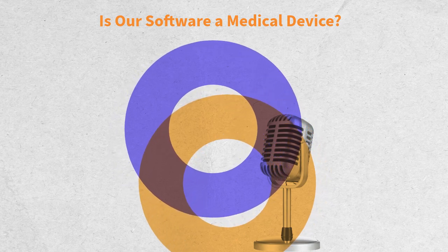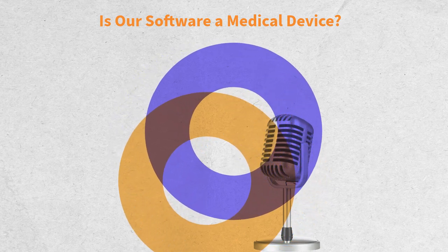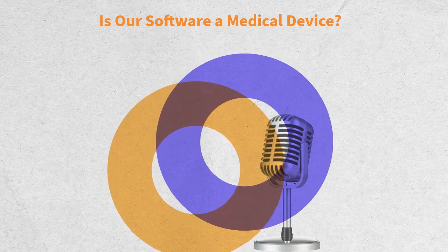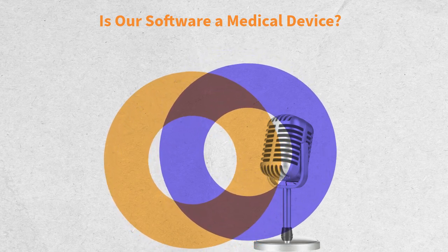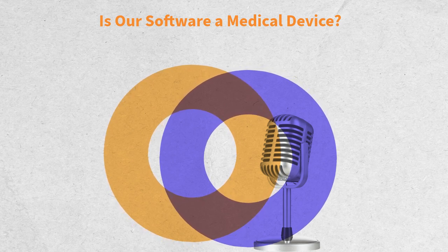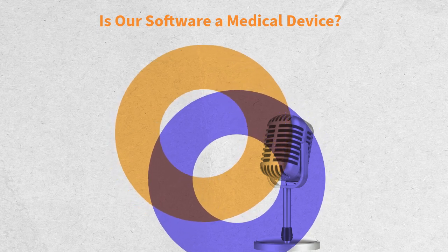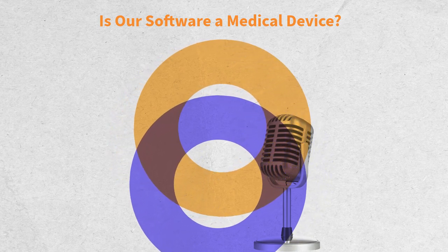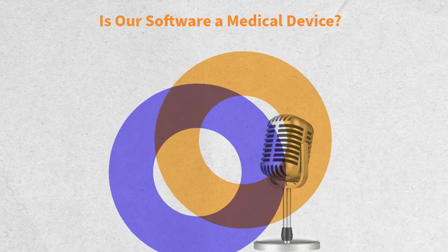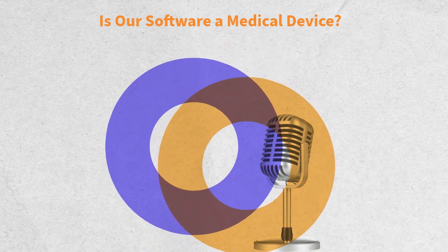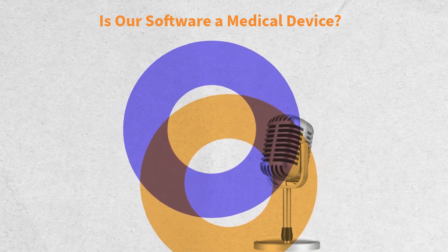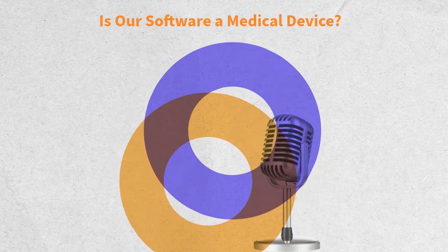Which are the European regulations applying to medical software? On the European front, the main norms are the following: MDR 2017-745. It defines the safety and performance requirements for all medical devices, including software. GDPR for the protection of health personal data.